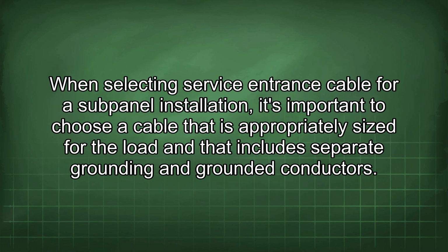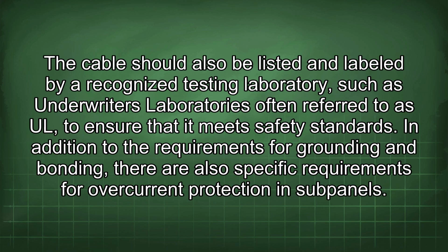When selecting service entrance cable for subpanel installation, it's important to choose a cable that is appropriately sized for the load and that includes separate grounding and grounded conductors. The cable should also be listed and labeled by a recognized testing laboratory, such as Underwriters Laboratories, often referred to as UL, to ensure that it meets safety standards.